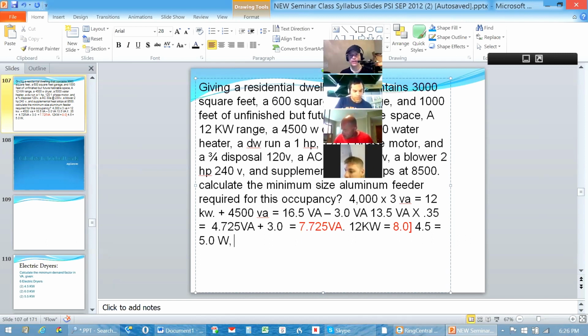So water heaters fall in that category, but you have to have a magic number of at least 4 of those fastened in place to be able to take any kind of derate. So we're really looking at just the 4,500 nameplate rating. Excuse me, I gave you 5,000 on the water heater, so we'd have 5,000 watts for the water heater straight across.